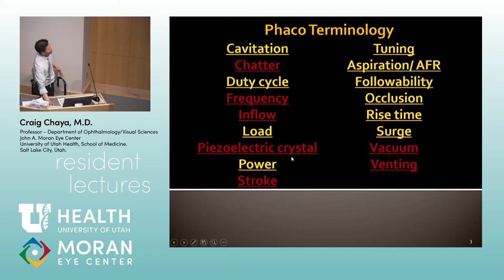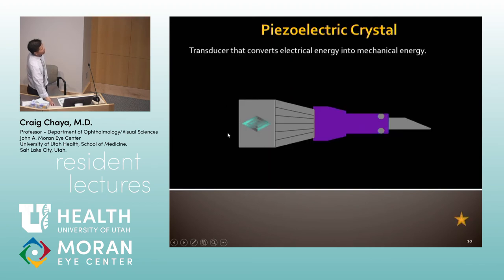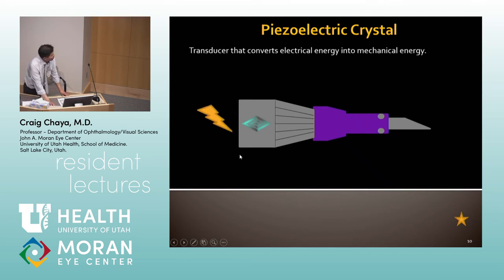The piezoelectric crystal is part of the phaco tip that moves in ultrasonic motion to create that back-and-forth motion. There's an actual crystal that converts electrical energy into mechanical energy — electricity comes in, causes the crystal to vibrate, and your tip vibrates then.